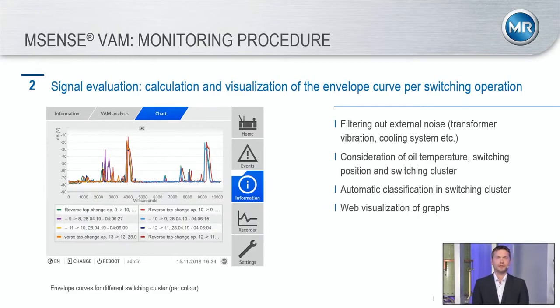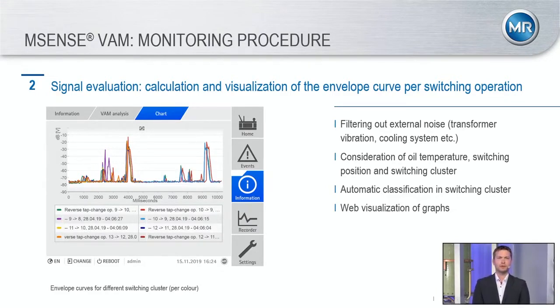In these examples you can see the influence of different switching clusters — each tap position has its own switching cluster and its own vibroacoustic shape and waveform. Notably, the violet curve shows a higher amplitude between 2 and 3 seconds compared to other signals. The rest of the signals are more or less similar, with some slight time-frequency shift which could come from different reasons.